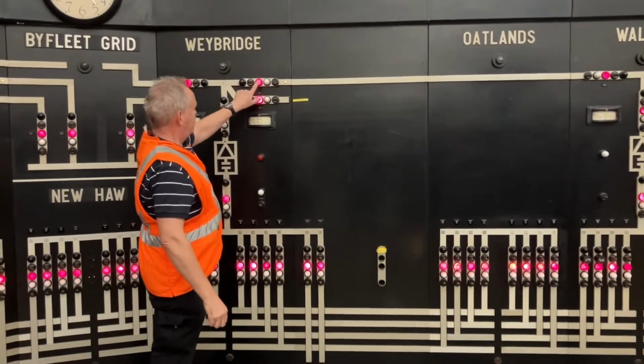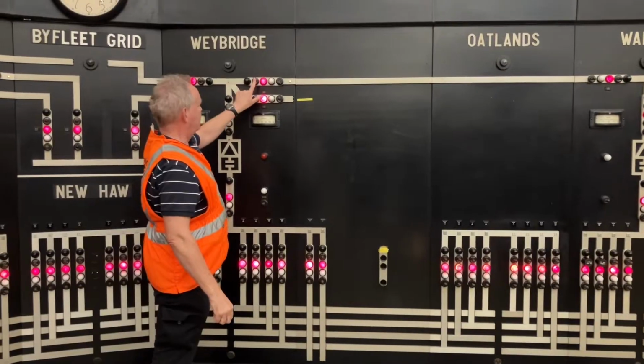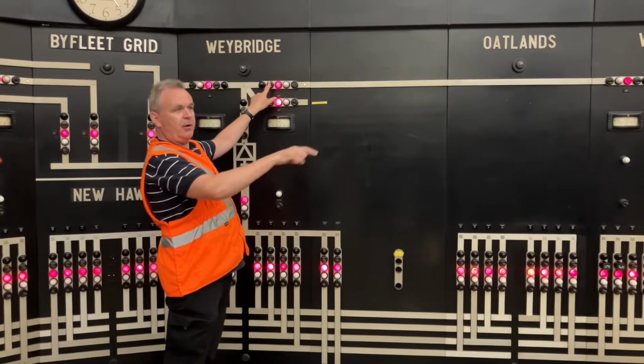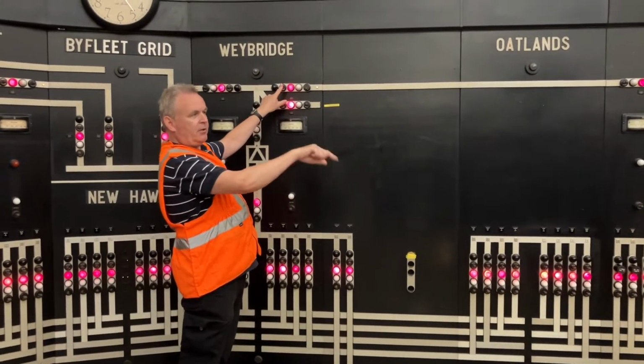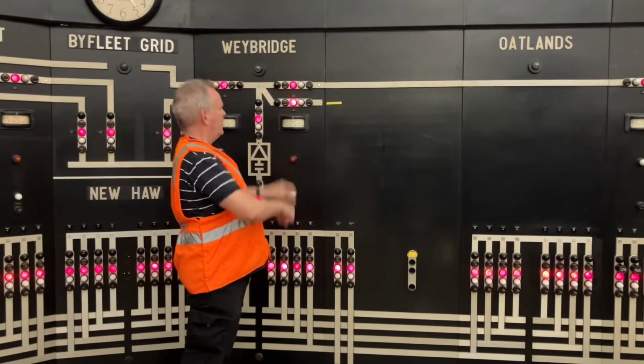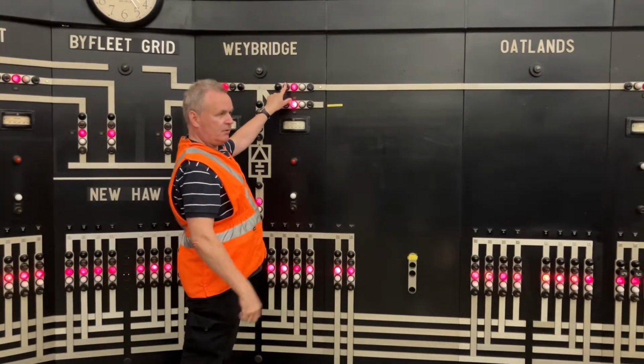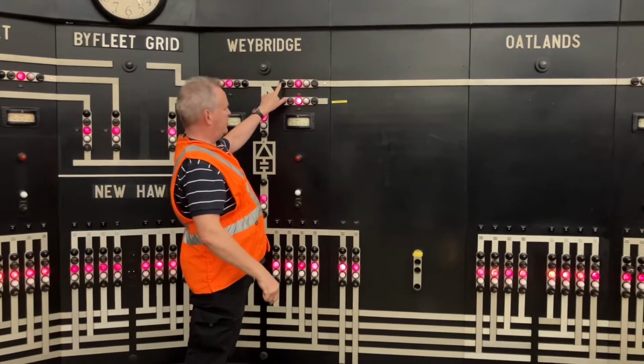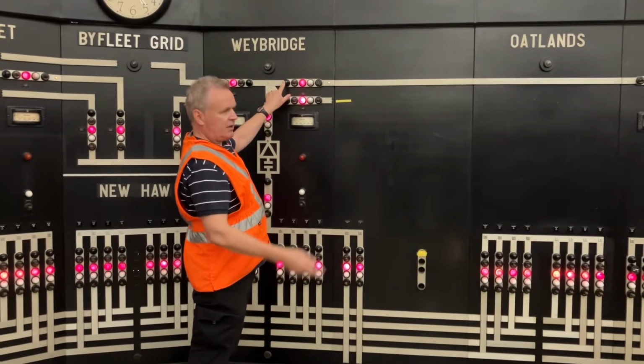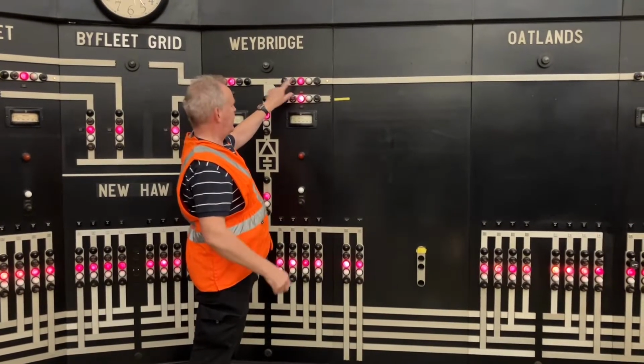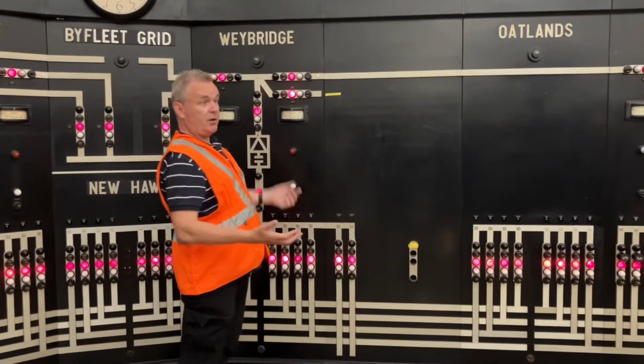In this case, we want to open it, so we give a pulse. We've now connected in copper from here down a little pilot cable to the side, and we put a battery pulse down that cable to operate the circuit breaker. That instigates an opening command, making the light go from red to green to show the breaker is open.